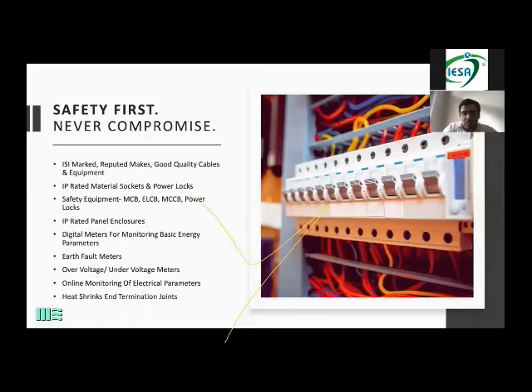Earth fault meters: we've spoken about what can go wrong with the earthing. It is very important, it is for the safety of humans. Earth fault meters are also available, which can be put on your panels too. All those things are available in the market. It is not that these things are not available. They are being used everywhere also. Over voltage, under voltage meters, again, they are available.